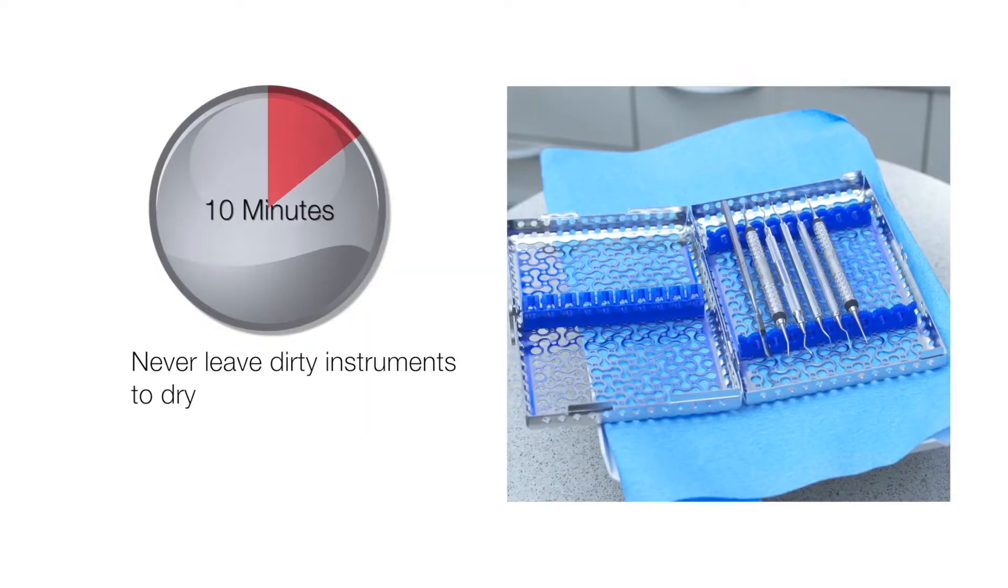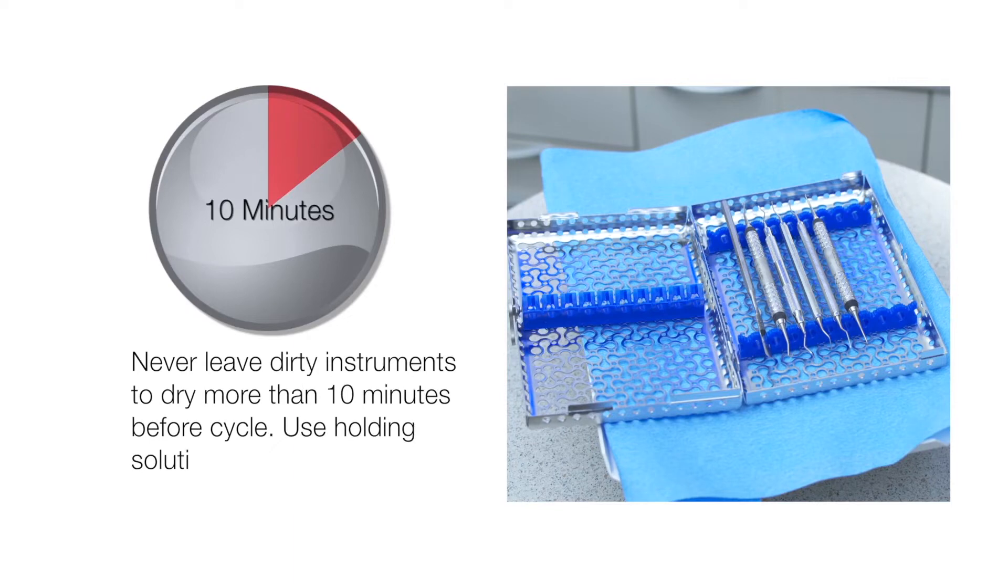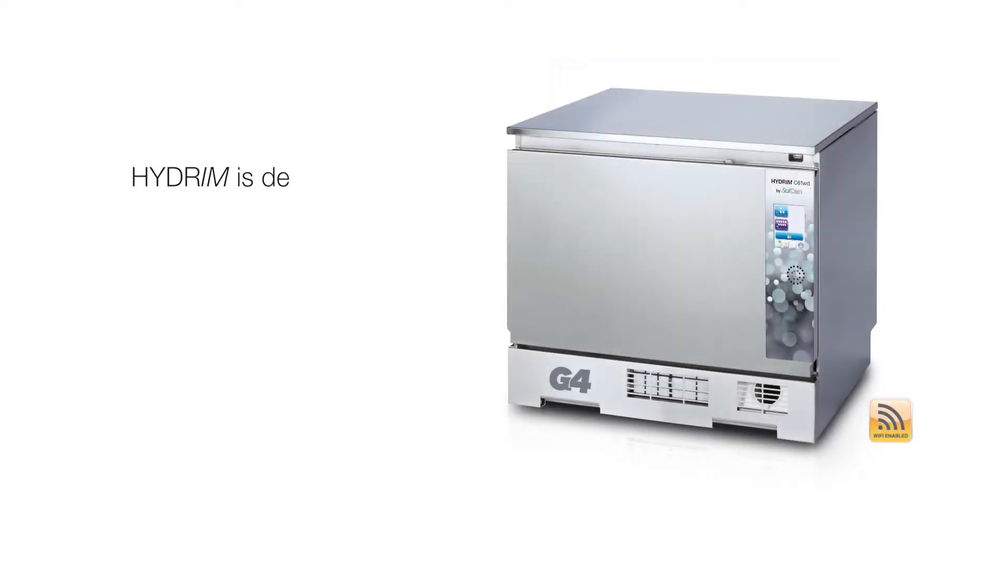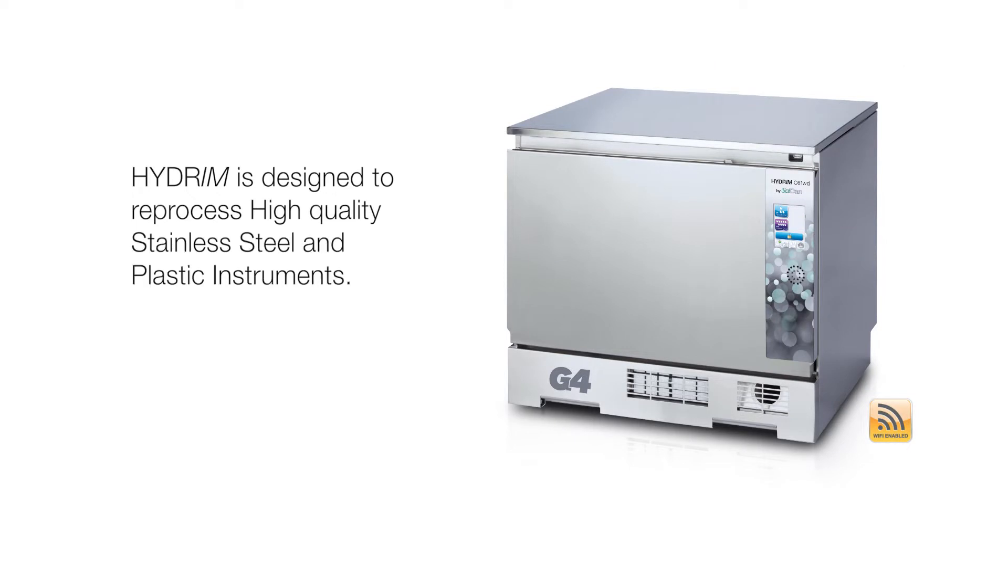Never leave dirty instruments to dry more than 10 minutes before cycle. Use P1 rinse and hold program when required. HYDRIM is designed to reprocess high quality stainless steel and plastic instruments.